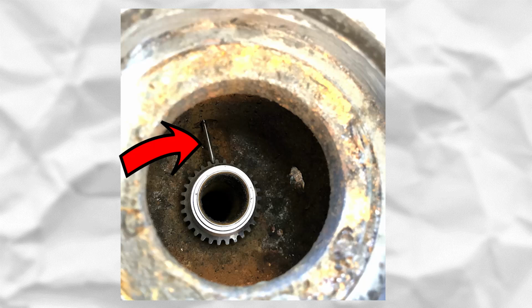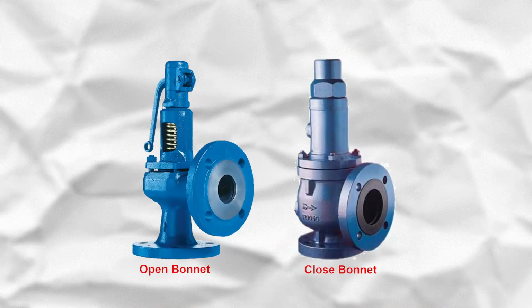In broad terms, spring specifies when PSV opens and blow-down ring determines when PSV closes. PSV bonnet might be open or closed. In some applications, such as hot steam services, we tend to consider an open bonnet to let the spring be exposed to the air in order to reduce the heat radiation. For sure, in toxic or corrosive services, you are not permitted to use an open one because in case of possible leakage, it poses a lot of dangers to the environment.